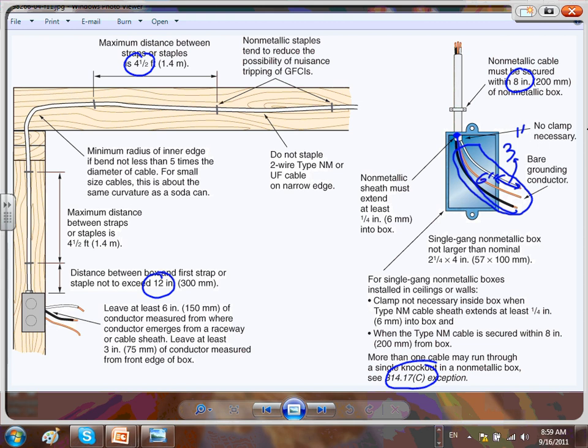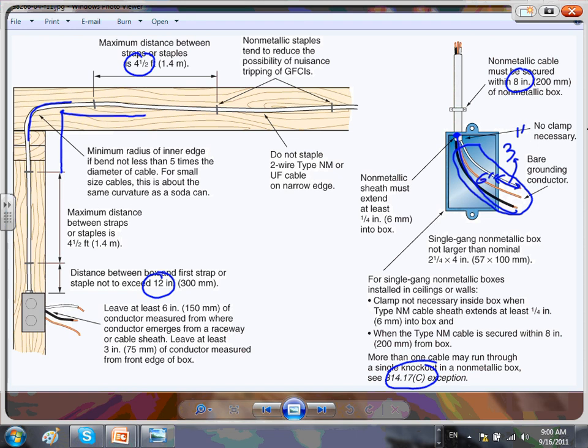Can you explain the rationale of the curvature requirement? The idea is this: the alternative is to come and make a sharp angle. From a scientific point of view, when you make a sharp angle it creates more resistance in the wire, and you could also damage the insulation. The code is primarily about protecting the insulation, because you could easily bend it and damage the insulation. The rule is five times the diameter of the cable.